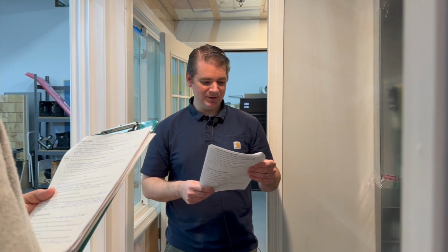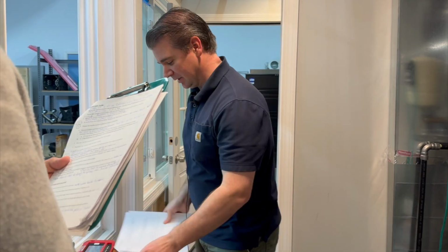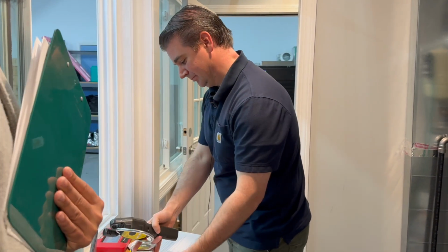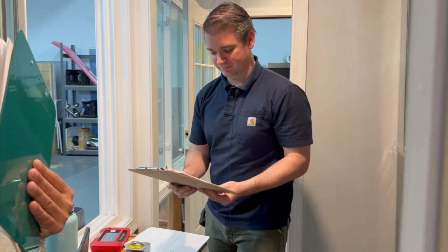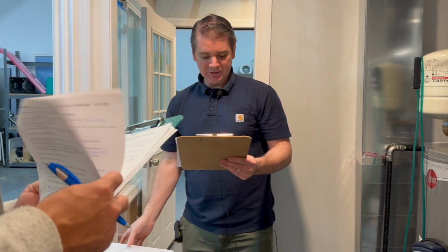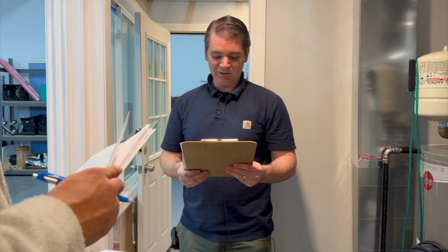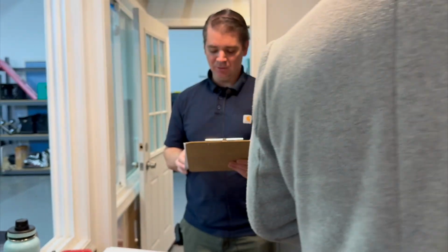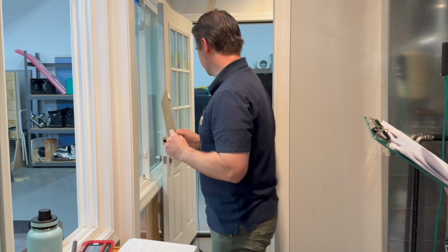Set up the house for combustion safety testing in the CAZ. All right, so now at this point, I can swap to my other paper. Prepare the house for worst case and natural conditions. For fireplace and wood stoves, it must be cold. Close the dampers. Put wet paper on any ashes. Close exterior doors and windows.